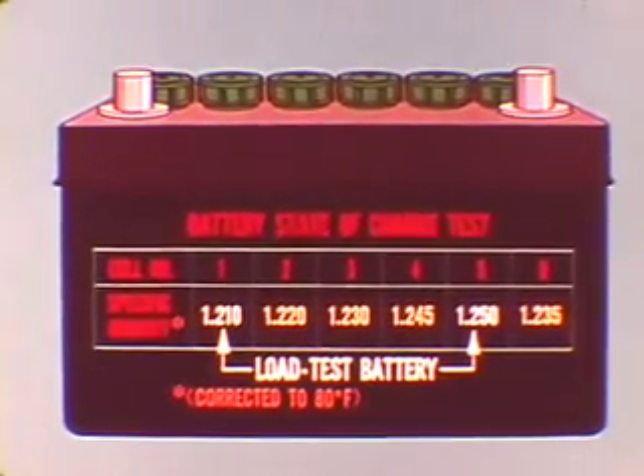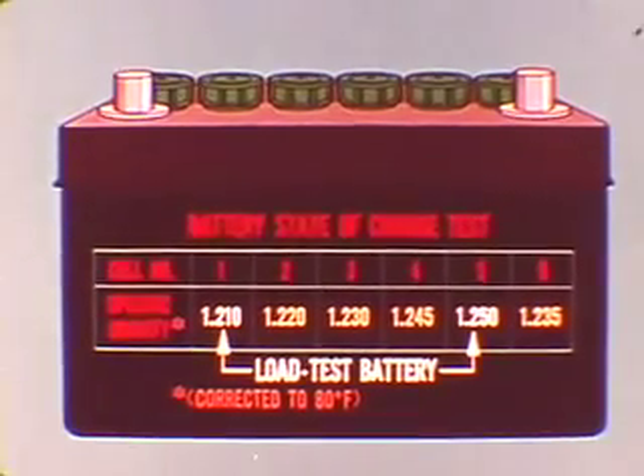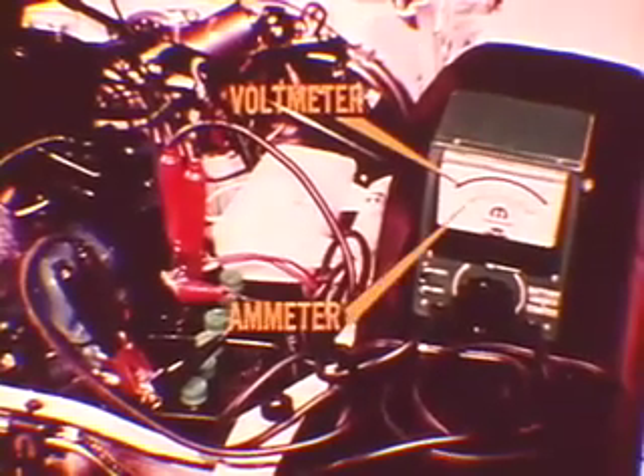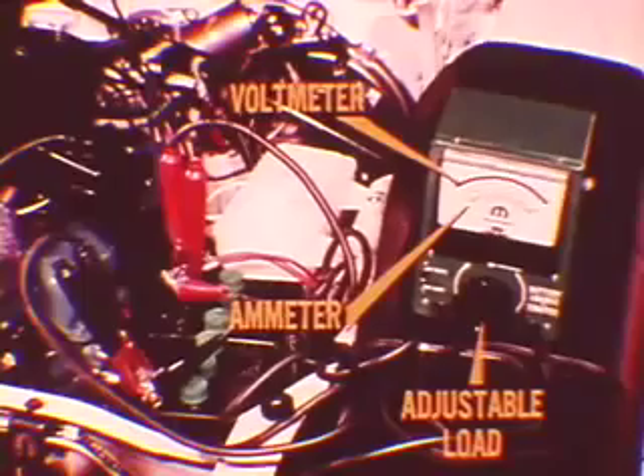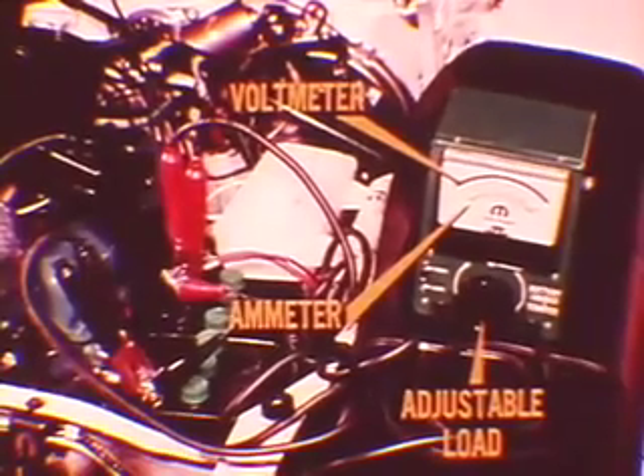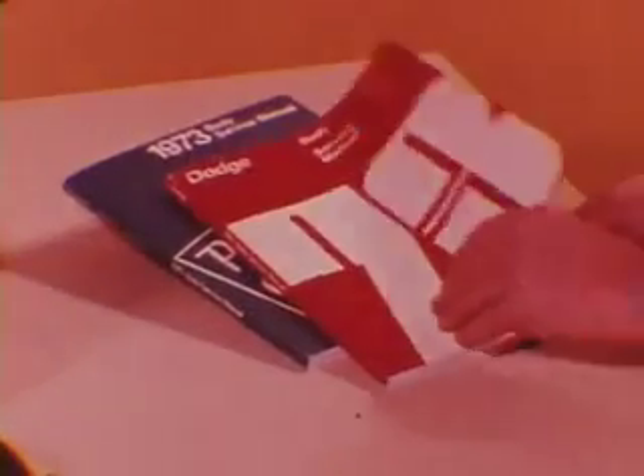This test checks the battery's ability to deliver electrical power. It determines whether or not the battery is still serviceable. The battery load tester includes a voltmeter, an ammeter, and an adjustable load or resistance. Hookup connections are described in the instructions that come with the tester. You'll find a lot more information on battery service and circuit testing in this month's reference book.